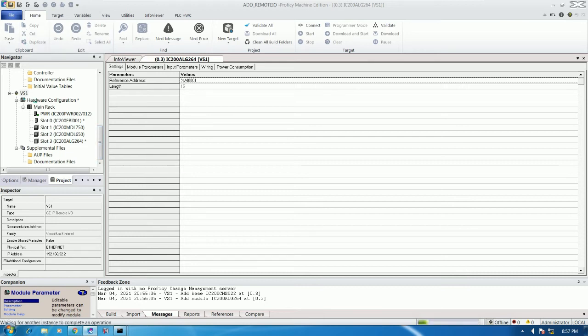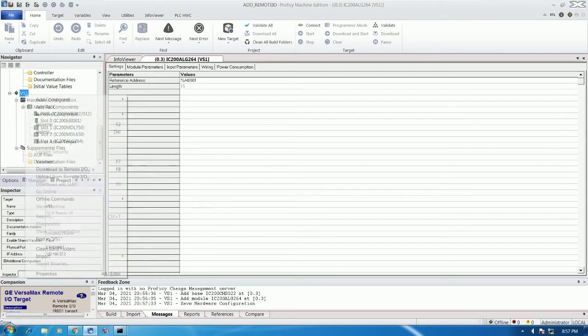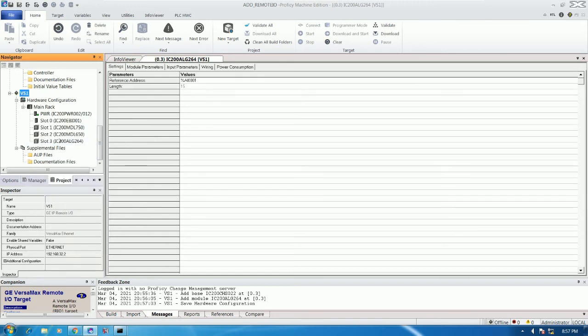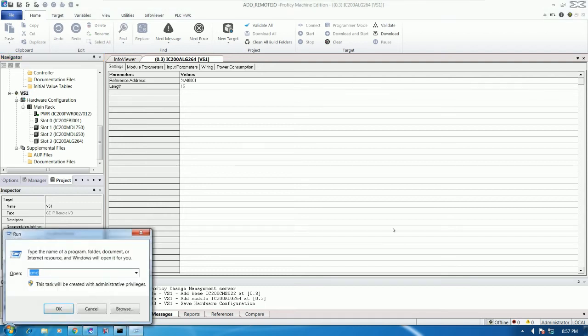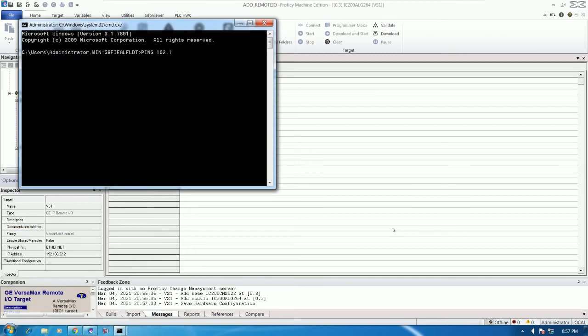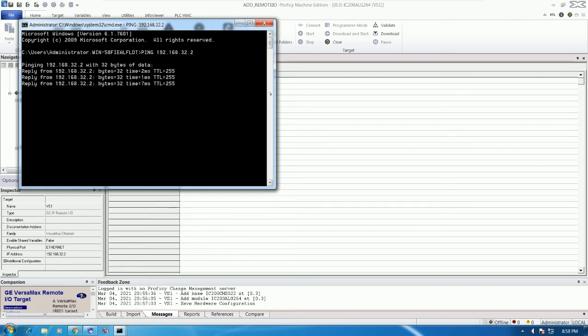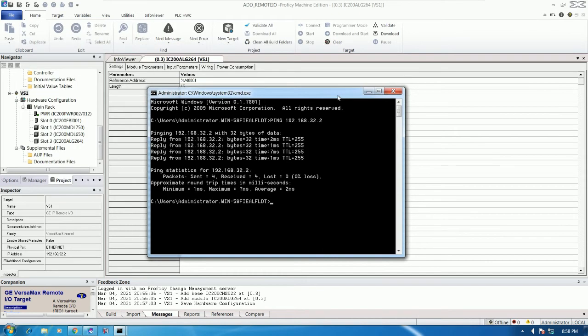We need to save the project and then download to the VersaMax I/O. Right-click and set the active target. I will disconnect the LAN cable from the CPU and connect it to the remote I/O which has IP 192.168.32.2. I can ping it to test. Ping 192.168.32.2 — we can ping successfully, which means we can connect from our PC to the remote I/O module.